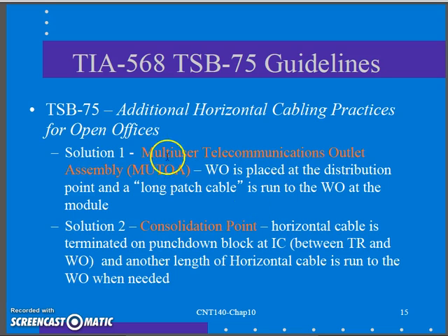TSB 75 recommended two things. Solution one, the multi-user telecommunication outlet assembly solution, or solution two, the consolidation point solution. Those are actually the two I just scrolled to in the standard to show you. These have been incorporated. With the multi-user telecommunication outlet assembly, or MUTOA, I'm basically going to place the work area outlet near where my computers are going to be and use a long patch cable from the computer up to the outlet. So I'm going to put an outlet near, but I'm going to end up using long patch cables. And the long patch cables might actually go from above the ceiling down through the channels into the computer.